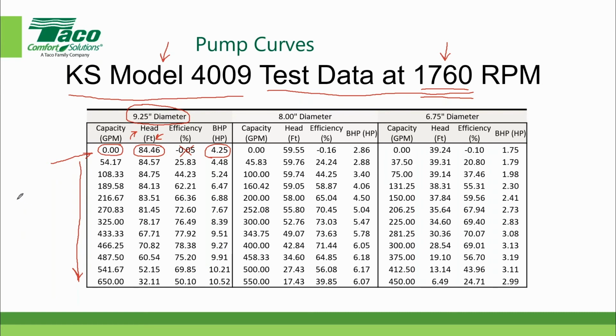Now, once we collect the data at 9.25 inch impeller diameter, we stop the test, isolate the pump, we take the pump apart, and we take out the 9.25 inch diameter impeller. We install the next size down, in this case 8 inches, and then we repeat the test data. And then we disassemble the pump one more time, put another impeller in, in this case 6.75, and we repeat the test to collect the data. So that's how we collect the pump data.